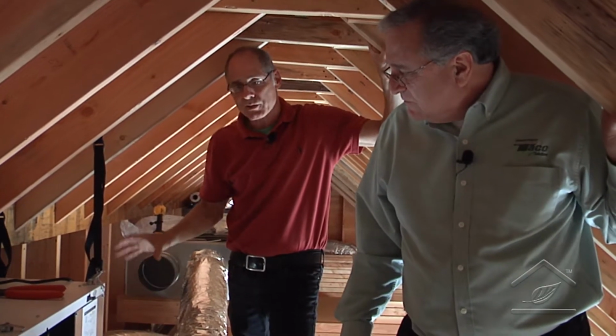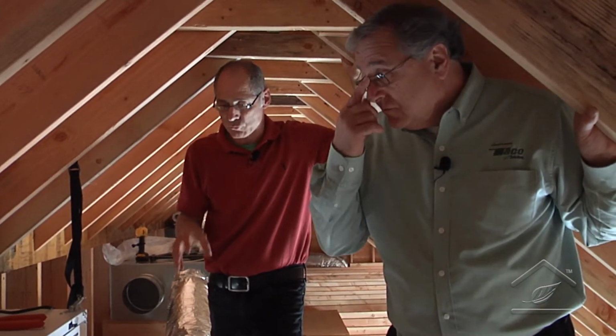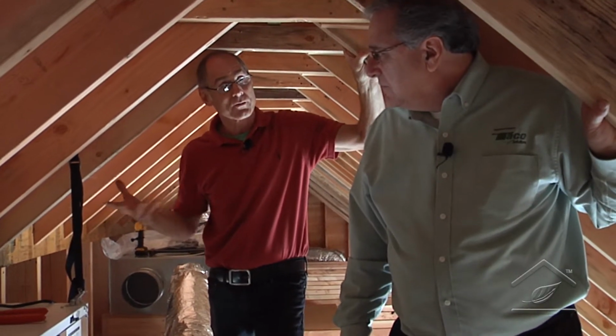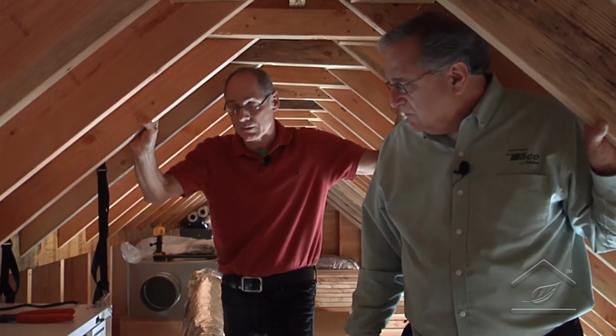There are many different ways that we could put that fresh air back in the building. You could do it in a stairwell, a common area. We typically don't put it in each room, but in a common area. Or if you actually have a mechanical system with ductwork, sometimes we just put it in the return of that, and that kind of diffuses through. Even if that system's off, that fresh air enters the building and will make its way through there. So that's how I did it in this case.